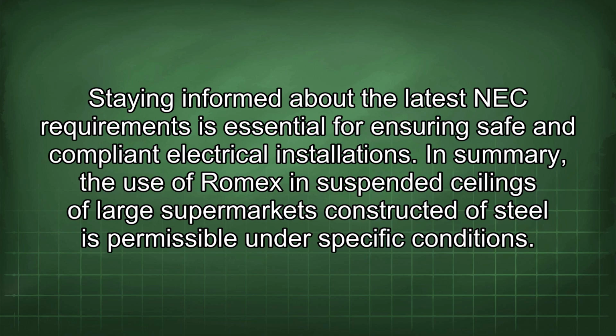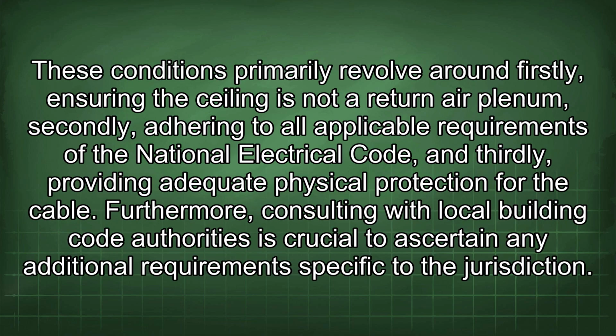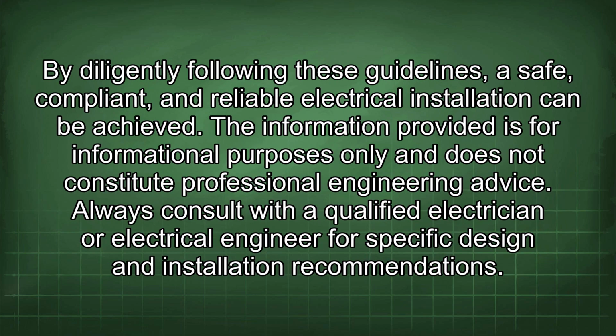In summary, the use of Romex in suspended ceilings of large supermarkets constructed of steel is permissible under specific conditions. These conditions primarily revolve around, firstly, ensuring the ceiling is not a return air plenum, secondly, adhering to all applicable requirements of the National Electrical Code, and thirdly, providing adequate physical protection for the cable. Furthermore, consulting with local building code authorities is crucial to ascertain any additional requirements specific to the jurisdiction. By diligently following these guidelines, a safe, compliant, and reliable electrical installation can be achieved.